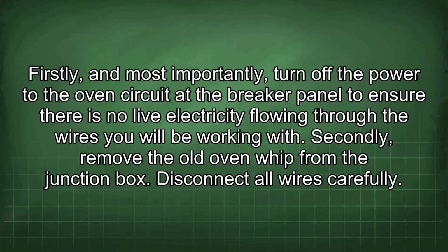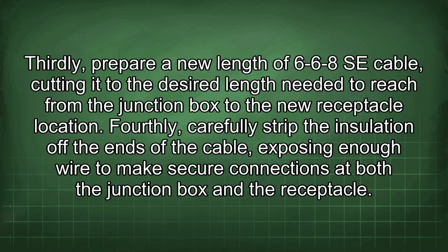Firstly, and most importantly, turn off the power to the oven circuit at the breaker panel to ensure there is no live electricity flowing through the wires you will be working with. Secondly, remove the old oven whip from the junction box. Disconnect all wires carefully. Thirdly, prepare a new length of 6-6-8 SE cable, cutting it to the desired length needed to reach from the junction box to the new receptacle location.